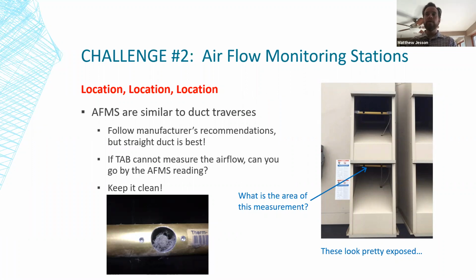And if we get calls for buildings that are having building pressure issues, this is one of the first things I'll look for. And in this particular picture, on top there's this huge air handling unit. So I had to get up on top of it, 10, 12 feet in the air or whatever, crawl inside a duct and crawl down 15 to 20 feet to get to this airflow station. And I wasn't at all surprised when I saw that it was this dirty. But often with these, you can clean them with compressed air or a little paintbrush. You don't want to spray Windex on them or something. But once you clean them off, often it'll just come right back to where it used to read, and the building will come under control. So first of all, if you can put it in a filtered airstream, please do. Second of all, make sure there's access to it and that the maintenance staff knows that this is something they should check on a regular basis. Sometimes I know that it's not feasible to get it in a filtered airstream.